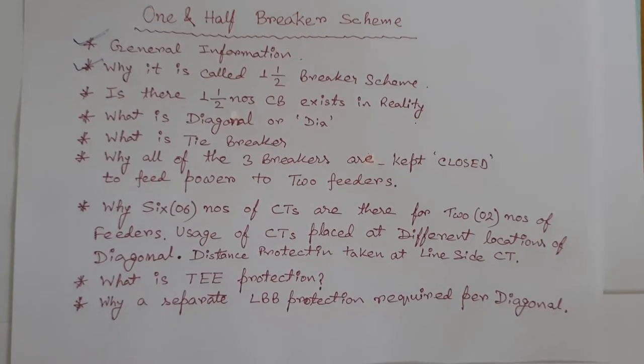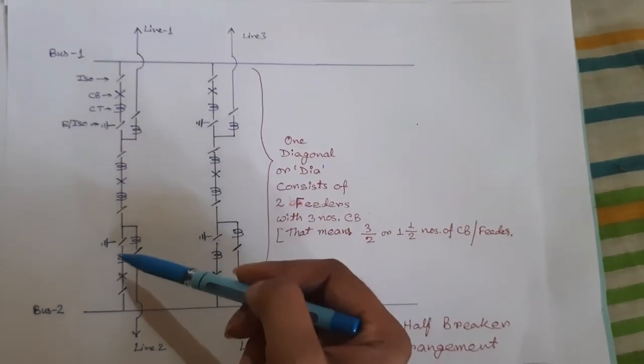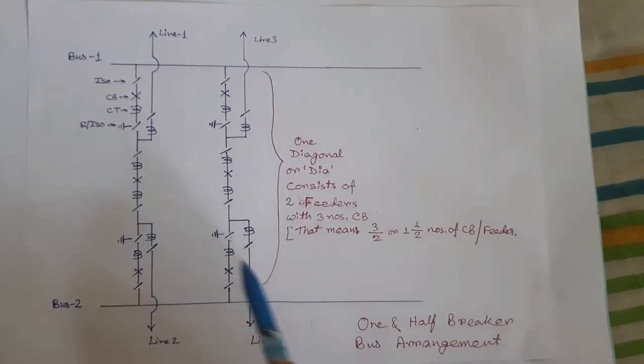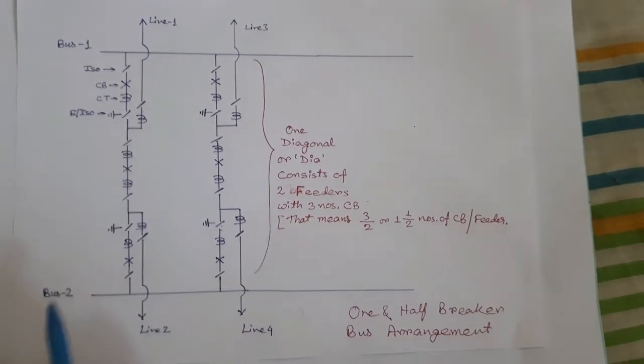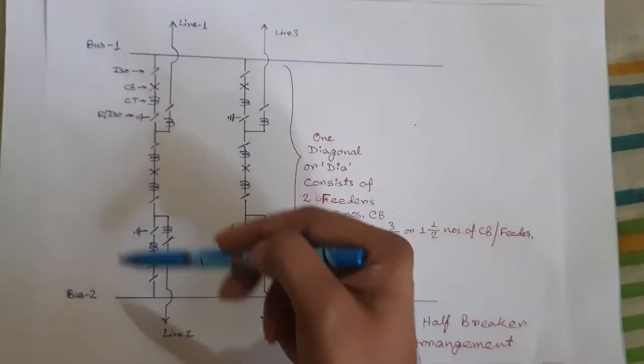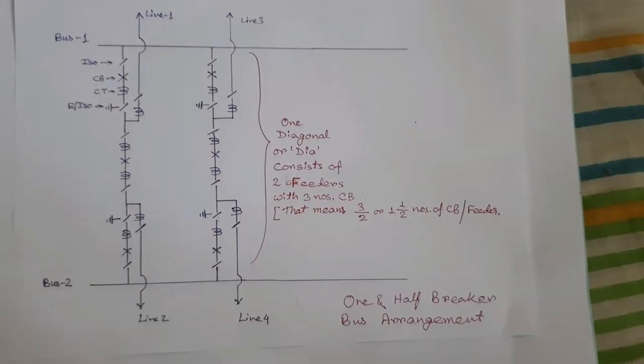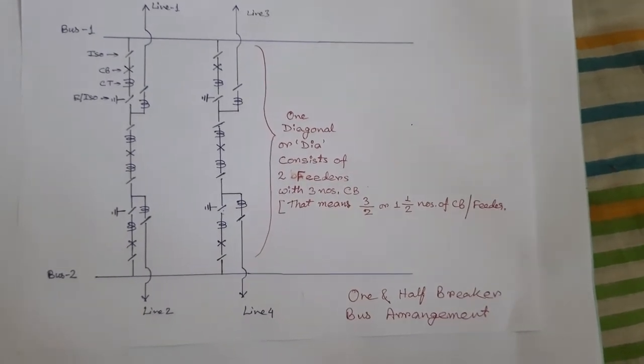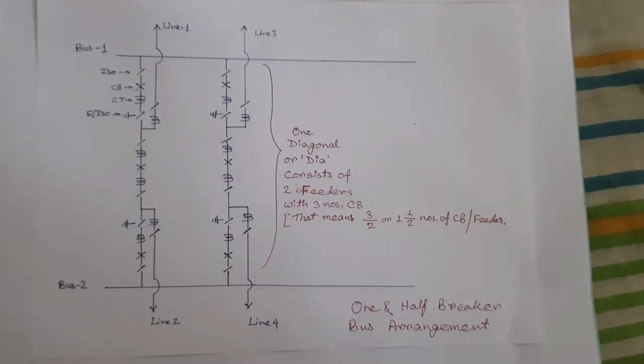Why is it called the one and half breaker scheme? This scheme is called the one and half breaker scheme because there are three circuit breakers for two feeders. This is a simple substation bus arrangement with two main buses and four feeders. For each set of two feeders, there are three circuit breakers. So for each feeder, three divided by two — that is one and half — circuit breakers are allotted. That is why it is called the one and half breaker scheme.